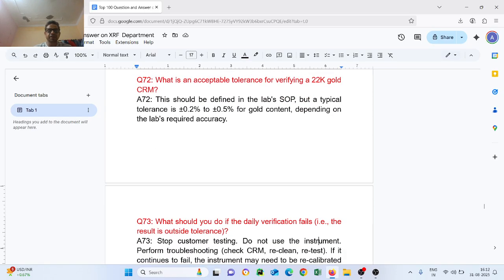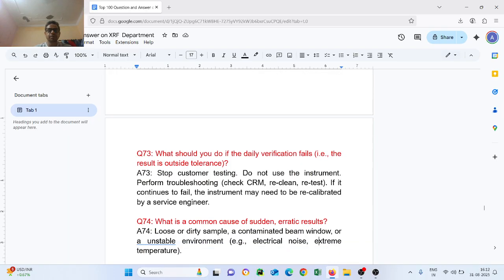Question number 73. What should you do if the daily verification fails? That is, the result is outside tolerance. Answer: stop customer testing. Do not use the instrument. Perform troubleshooting. Check CRM. Clean. Retest. If it continues to fail, the instrument may need to be recalibrated by the service engineer.